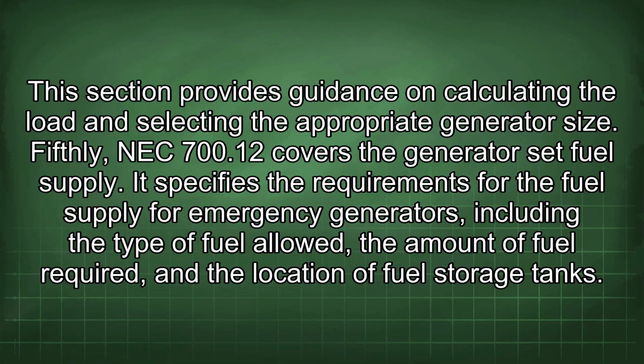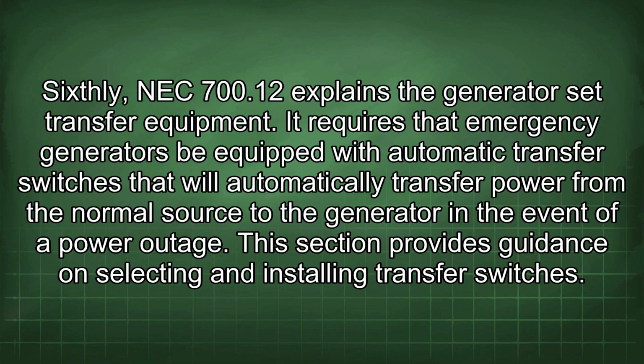Fifthly, NEC 700.12 covers the generator set fuel supply. It specifies the requirements for the fuel supply for emergency generators, including the type of fuel allowed, the amount of fuel required, and the location of fuel storage tanks. Sixthly, NEC 700.12 explains the generator set transfer equipment. It requires that emergency generators be equipped with automatic transfer switches that will automatically transfer power from the normal source to the generator in the event of a power outage. This section provides guidance on selecting and installing transfer switches.